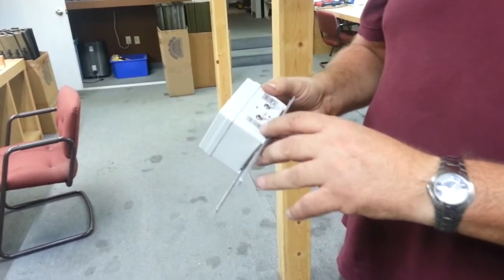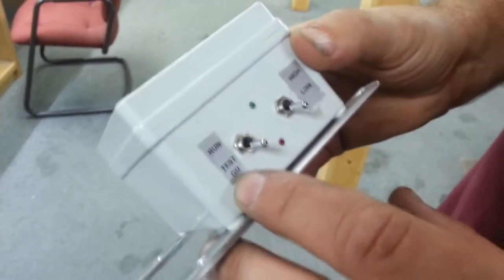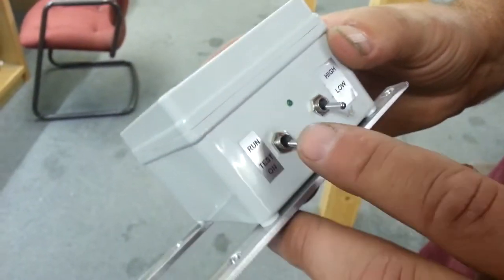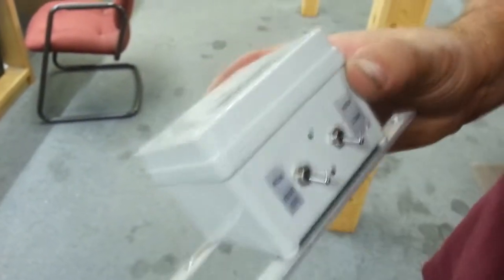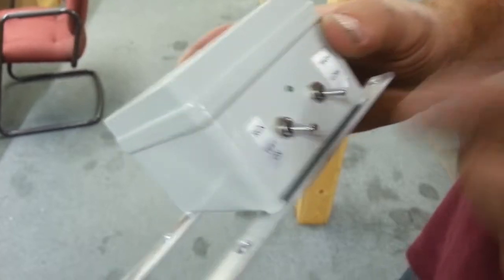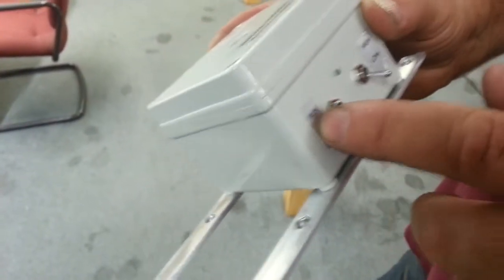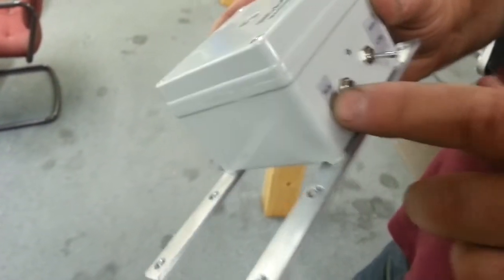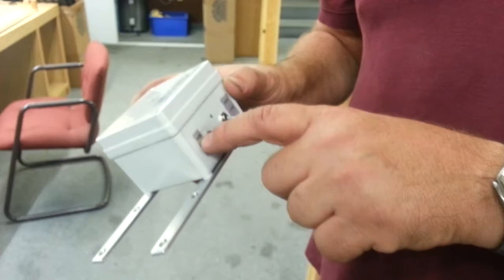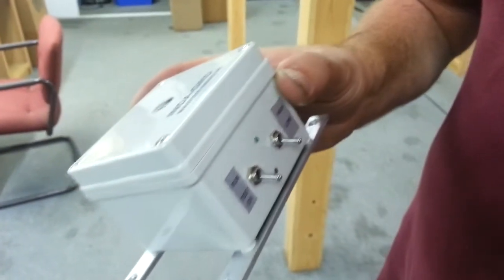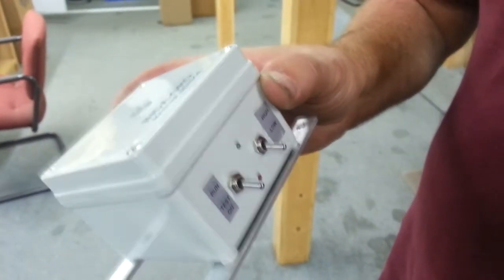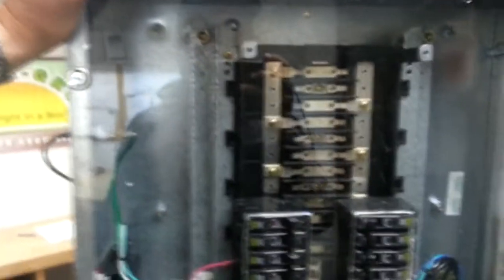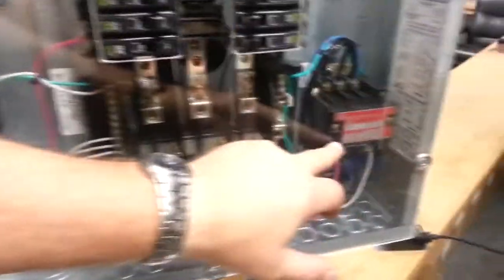And this has a run switch and a test on switch. We're going to have it in test on because in test on, it will activate in five seconds or 10 seconds. The run position will be five minutes. So that means you'll have a sustained condition for five minutes before this switch activates the panel, which this panel right here would be typical of what you'd see in a greenhouse. This one happens to be three phase and there's a lighting contactor here, which will control all the breakers.